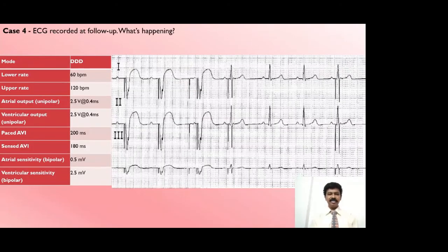And another patient, another DDD implant. So here is the tracing, what is happening. Definitely you can see pacemaker spikes and absent pacemaker spikes, and there is something happening here. The first 2 beats are A sense, V pace, the third beat is A pace, V pace, and definitely you see the fourth beat A pacing, but the atrium is undersensed, that is not sensed. Immediately after A pacing, you see an intrinsic beat followed by a ventricular pacing spike.